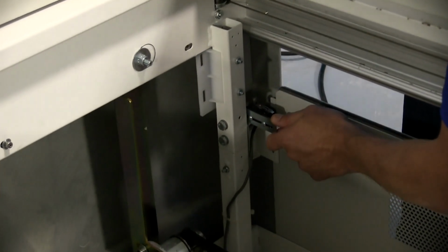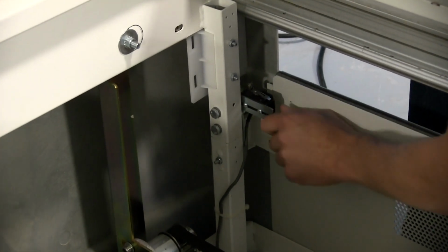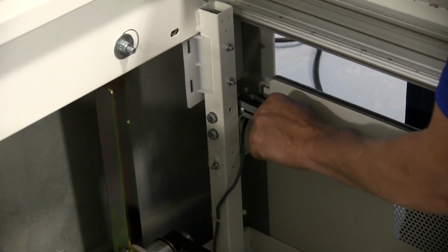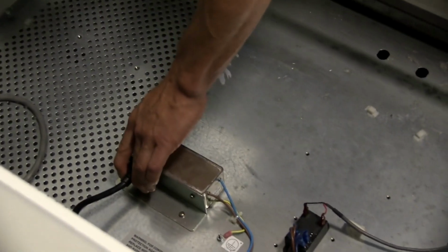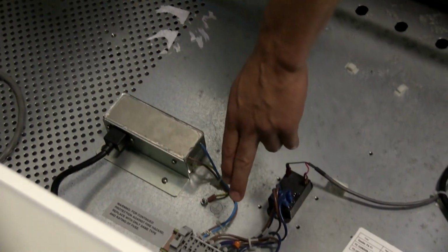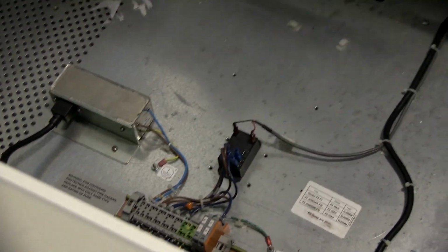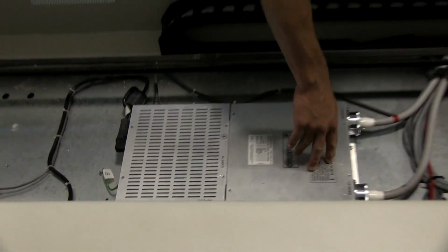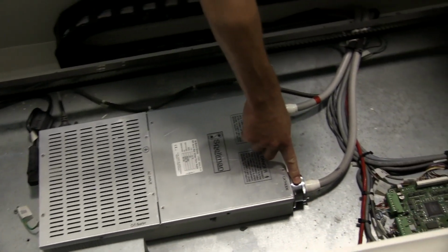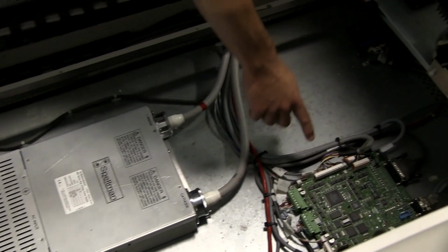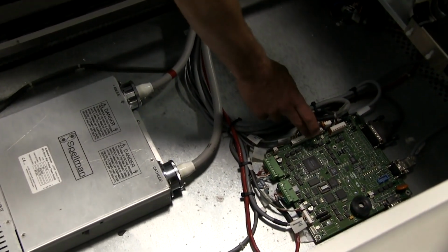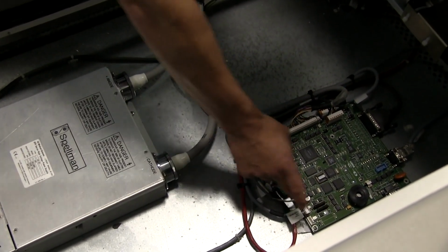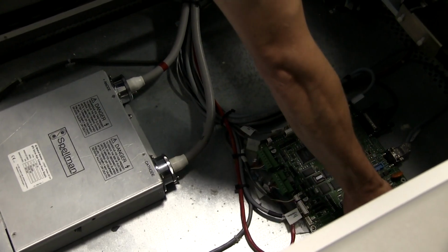Looking at your limit switches, making sure the bracket and the limit switch is secure. Looking at your incoming power, make sure that that's secure and any other connections on the DIN rail. We have already looked at the connections and re-siliconed on the high voltage power supply. Looking at your CSBC board, make sure all the connections are good all the way throughout the CSBC.